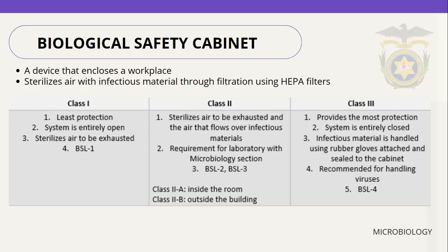So first we have the Class 1. It offers the least protection, the system is entirely open, and it sterilizes air to be exhausted. So this is mainly for BSL-1.